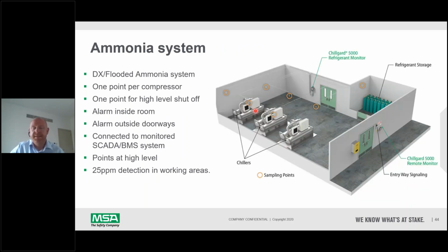So an ammonia system is slightly different, only because the gas goes to the ceiling. So this is a typical ammonia chiller room. The Chillgard 5000 is still located on the wall, but all of the detection points are at high level at the ceiling. This is hugely beneficial for calibrating and maintenance, because all of the maintenance actually happens at the wall here at the refrigeration monitor. The only thing that needs to happen is that a filter at the end needs to be changed.